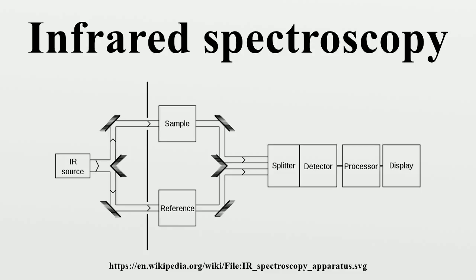Fourier Transform Infrared Spectroscopy (FTIR) is a measurement technique that allows one to record infrared spectra. Infrared light is guided through an interferometer and then through the sample. A moving mirror inside the apparatus alters the distribution of infrared light that passes through the interferometer. The signal directly recorded, called an interferogram, represents light output as a function of mirror position. A data processing technique called Fourier Transform turns this raw data into the desired result: light output as a function of infrared wavelength. The sample's spectrum is always compared to a reference.